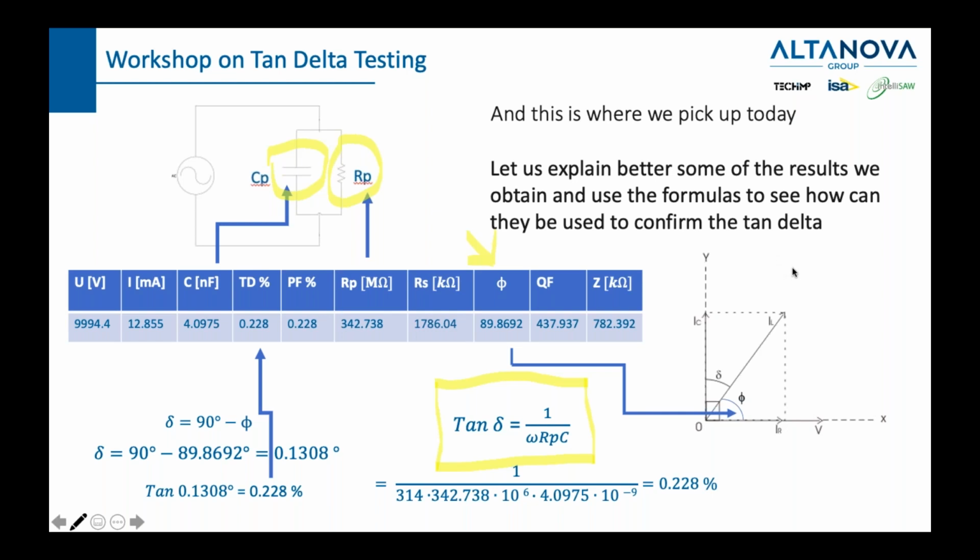Mr. Rabih is asking about very low frequency. It is not wrong. Very low frequency is a method mostly used on cables. We are here emphasizing more our measurement on transformers, but cables are also cables, since they have a higher capacitance, we use a lower frequency so that the device could be smaller. Again, question about C2, we will come to that.